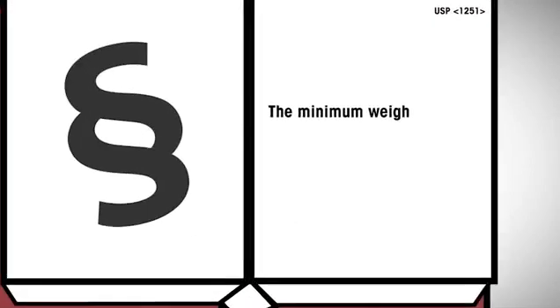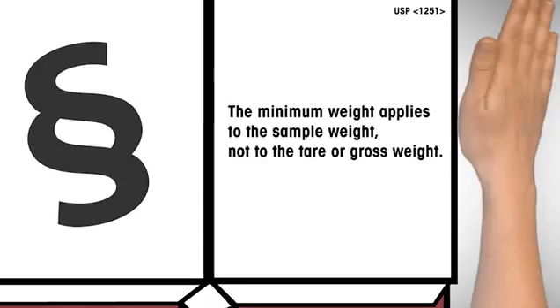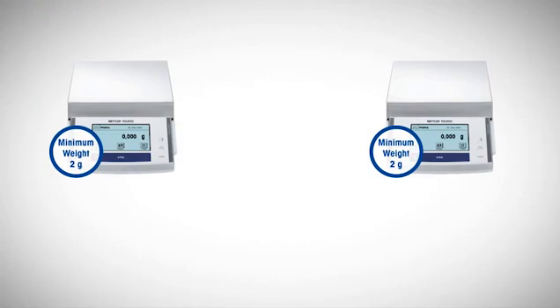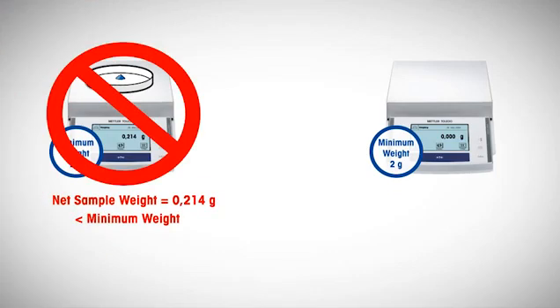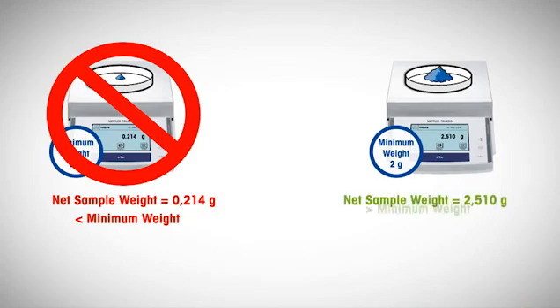The minimum weight applies to the sample weight, not to the tare or gross weight. A common misconception is that if the tare vessel is larger than the minimum weight, the weighing process is in compliance. It is now clearly stated that the net sample weight must be considered and not the gross weight.